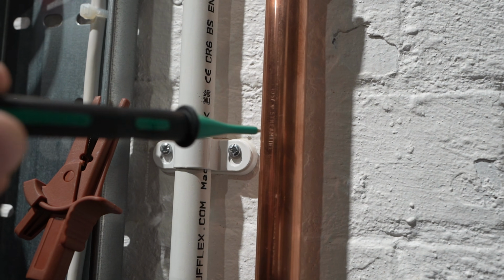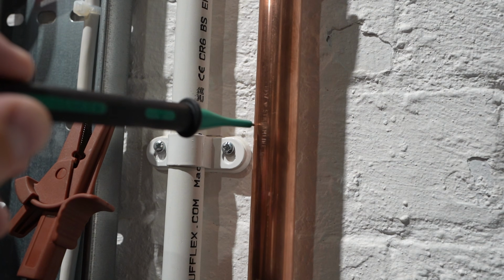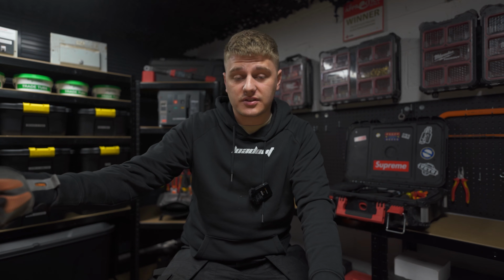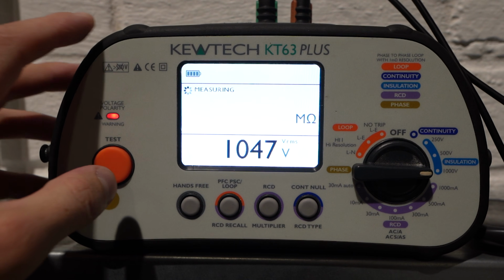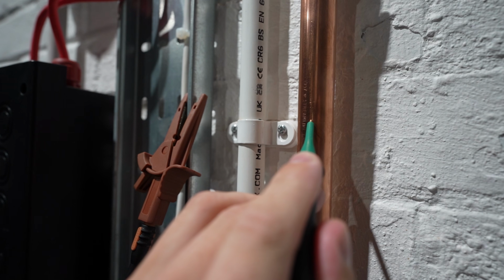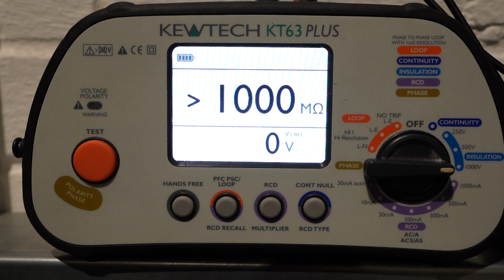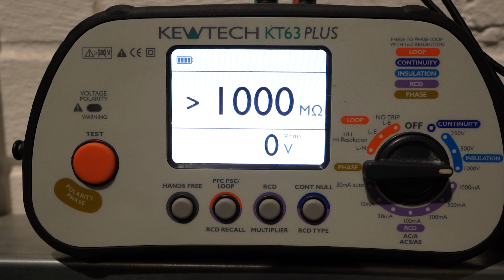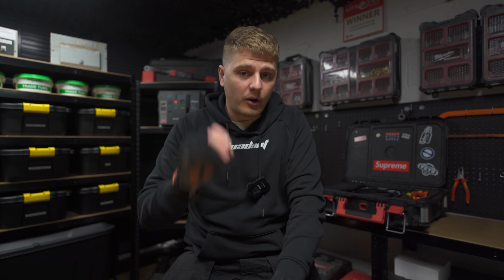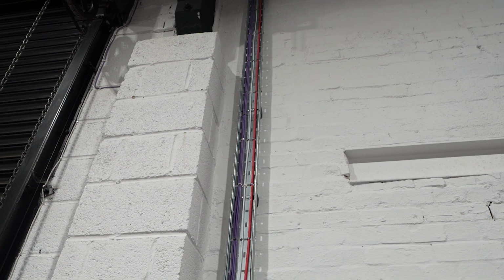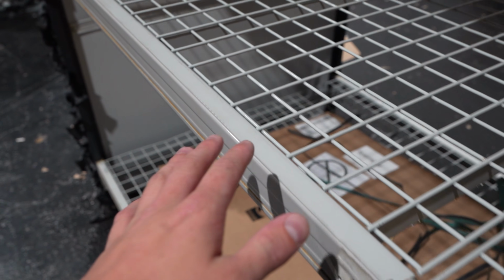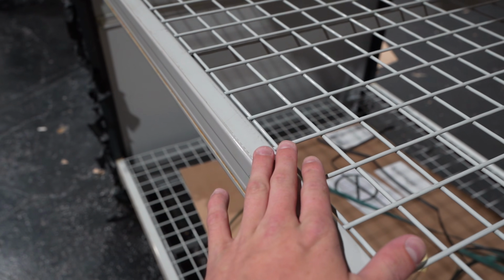So in this situation, you would test between what you're thinking is the exposed conductive part and the closest earth path, so something that you definitely know is connected to true earth, and do an insulation resistance test between those. Anything over 0.03 mega ohms you would consider not an extraneous conductive part, and therefore it wouldn't need bonding. Now again, apply the definitions and a bit of common sense before you just go around testing everything. A lot of stuff is insulated from earth, so just think about it before you do it, because you may be creating more problems than solving them.